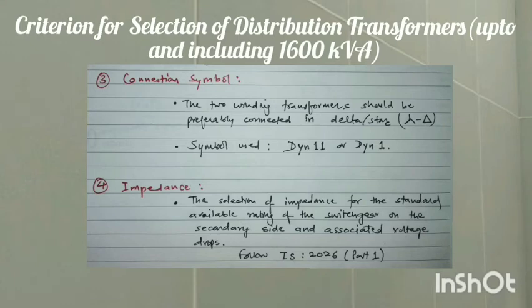Fourth, impedance. The selection of impedance is based on the standard available rating of the switchgear on the secondary side and associated voltage drops. More information for this is given in IS Standard 2026 Part 1.